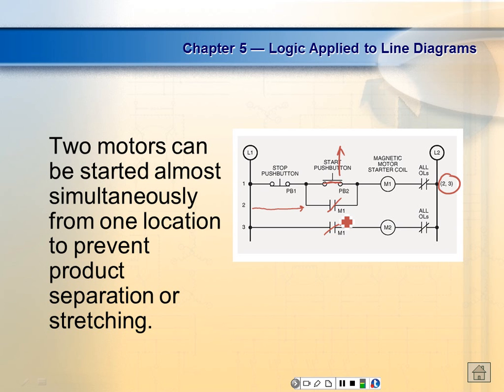Standard say, I mean, we could use the M1 auxiliary contact. Now this would be an auxiliary contact, right? You understand? Because this is not driving the motor. All this is doing is energizing the relay. The relay has those power contacts on it that run the motor over here in the power section of the diagram. Everybody understand that?